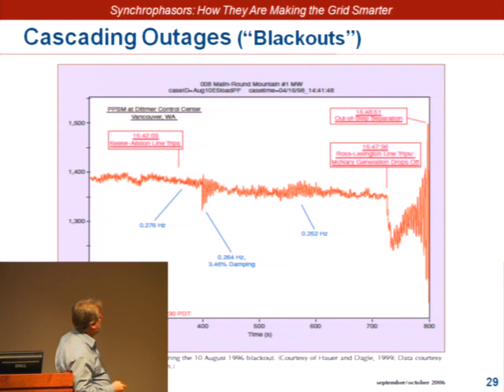Then something else happened here. It's not marked, but you see the ringing. And what's happening is the damping, which is measured in percent, is getting less. 3% is bad. I mean, it's getting very low. And it should not have rung like that. I mean, that signal should not ring like that. And things keep happening all along here until finally something happens, and that's all. It's over. The system can't take any more. Straw that broke the camel's back right there. So this is why wide area monitoring is good.